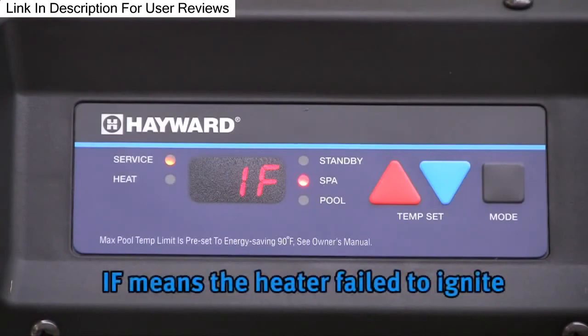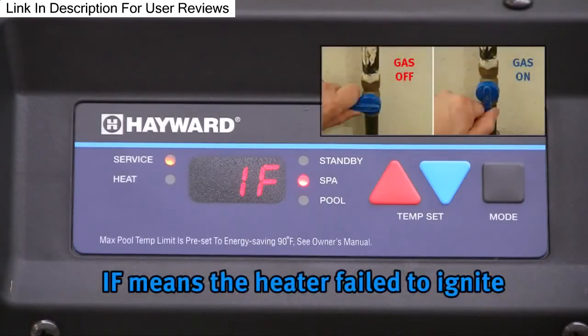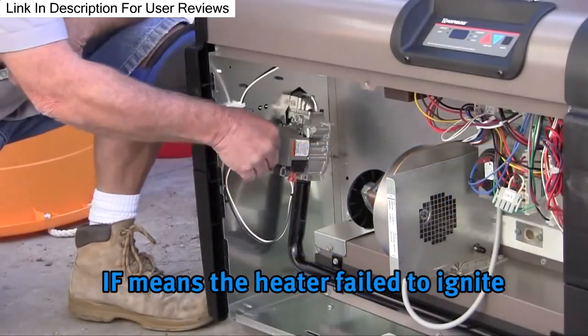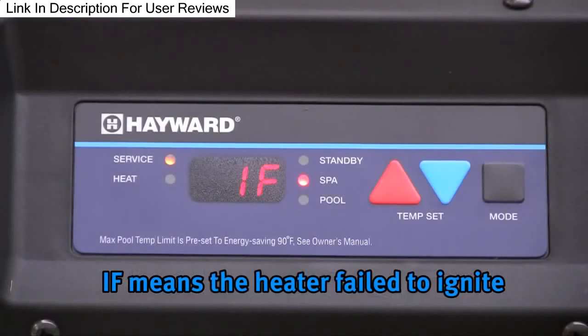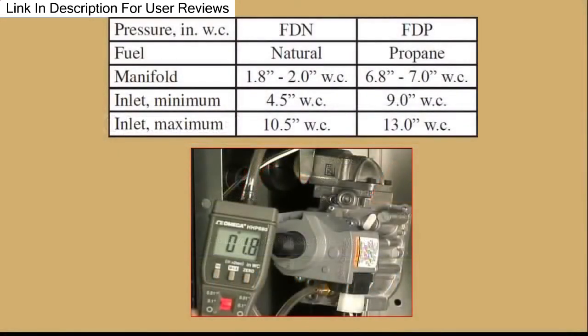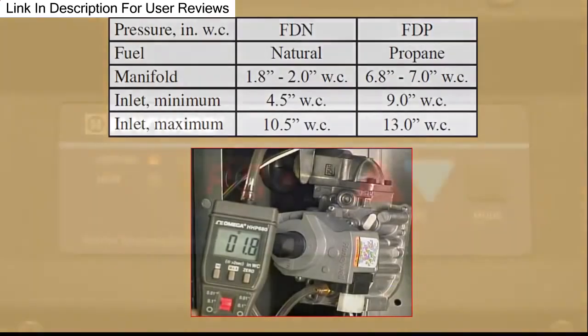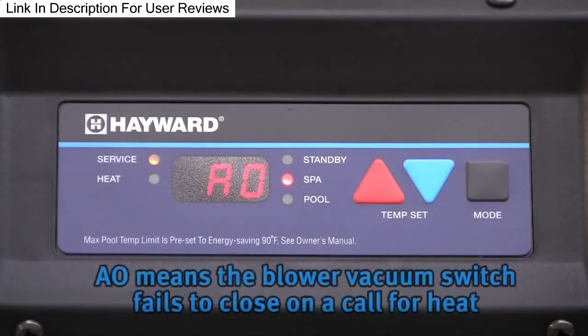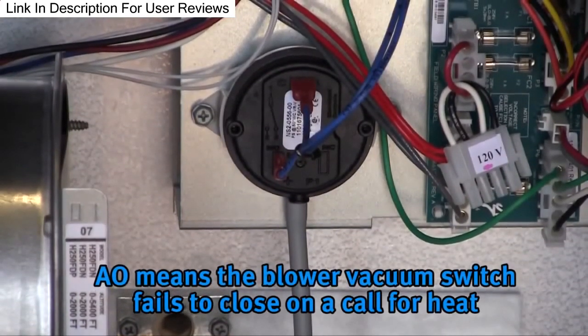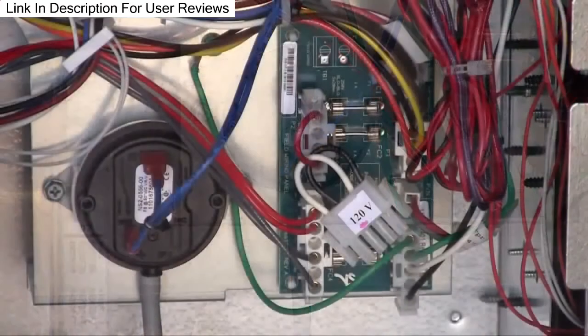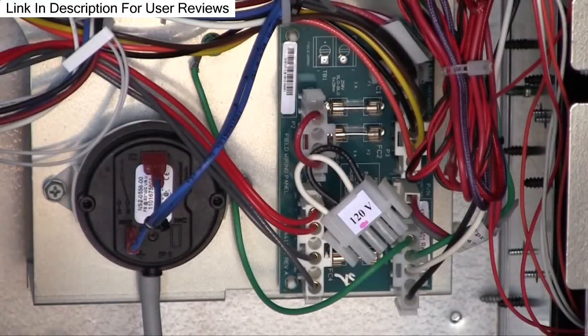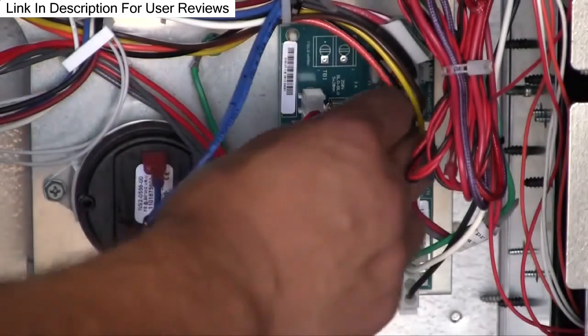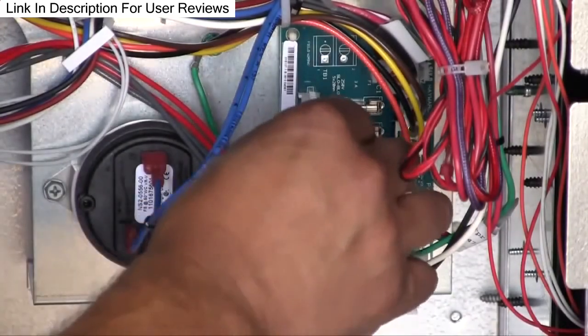IF. This means the heater failed to ignite. Make sure the gas shutoff valve is open. Make certain the gas control valve is in the on position. If all gas valves are open or on and the IF error still occurs, check the gas pressure. Instructions and required pressures can be found in the Service and Installation Manual or the Troubleshooting Guide. AO. The AO code is displayed when the blower vacuum switch fails to close on a call for heat. On new installations, this is sometimes caused by a failure to change the voltage selector plug from 240 volts to 120 volts when the heater is wired for 120 volt operation. Determine if the heater is wired for 120 volts, and if so, make sure the 120 volt plug is installed.